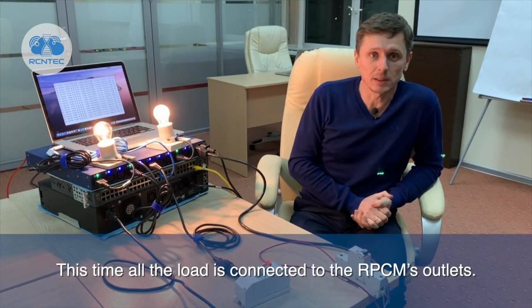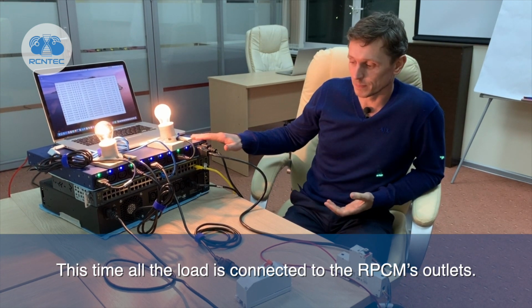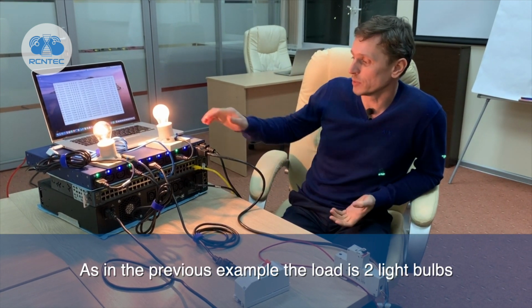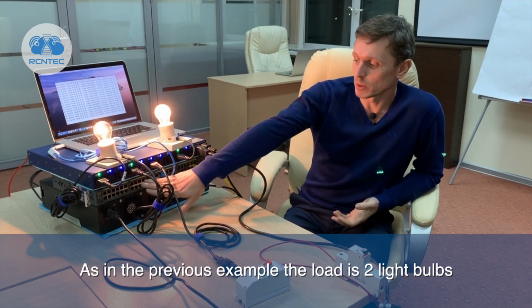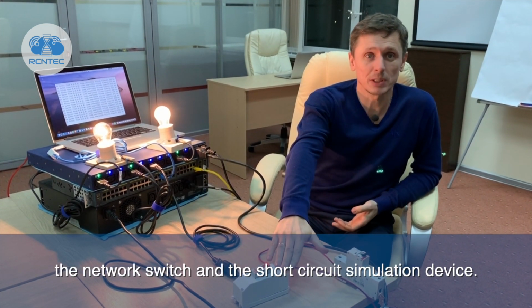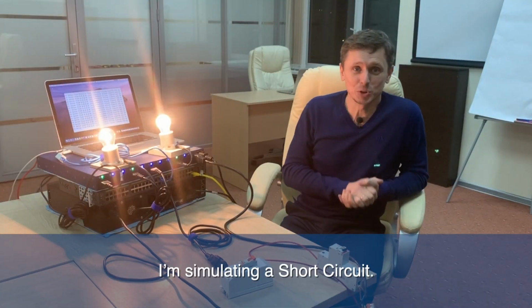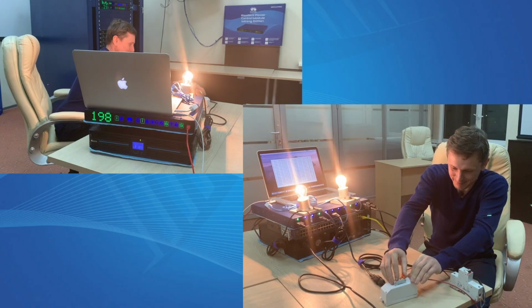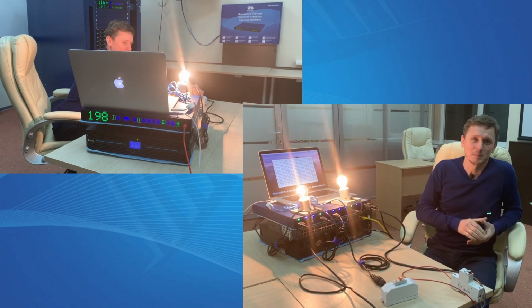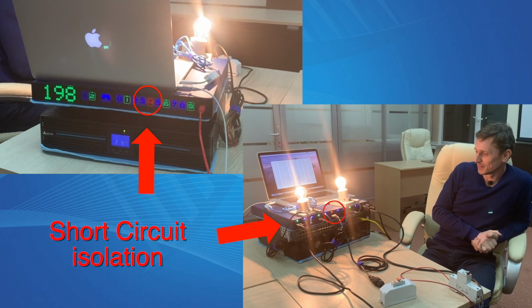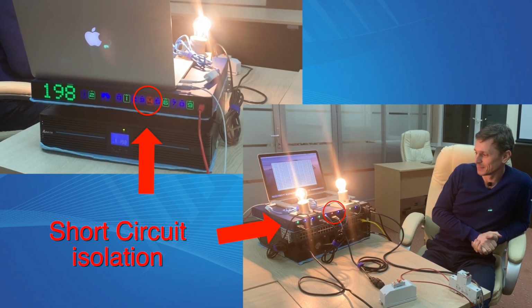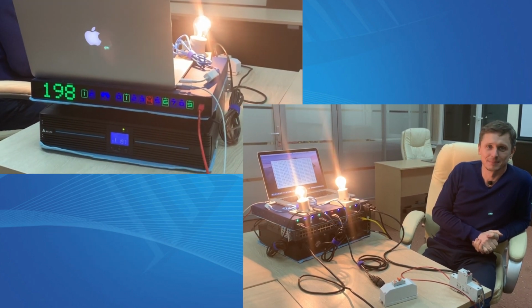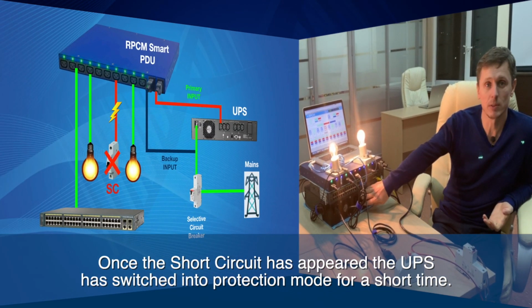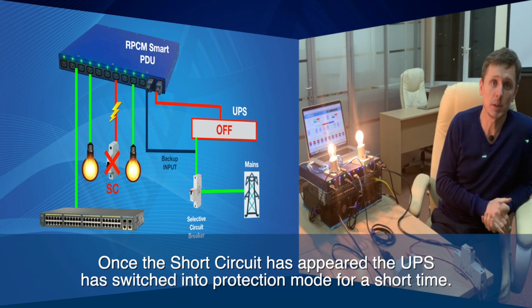This time all the load is connected to the RPCM's outlets. As in the previous example, the load is two light bulbs, the network switch, and the short circuit simulation device. I'm simulating a short circuit. What are we seeing?